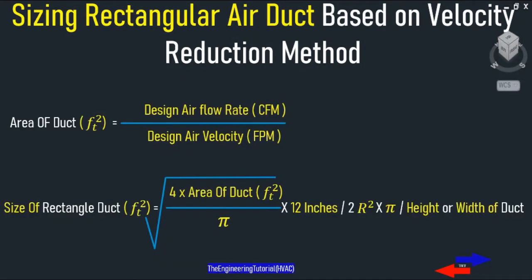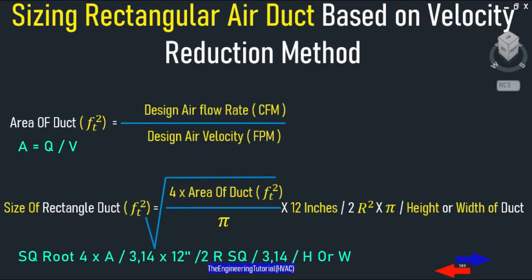To find all these branch and main duct sizes, we will use this formula: the air flow rate divided by air velocity, square root of 4 times area divided by pi, times 12 inches divided by 2, squared, times pi, divided by the height or width of the air duct.